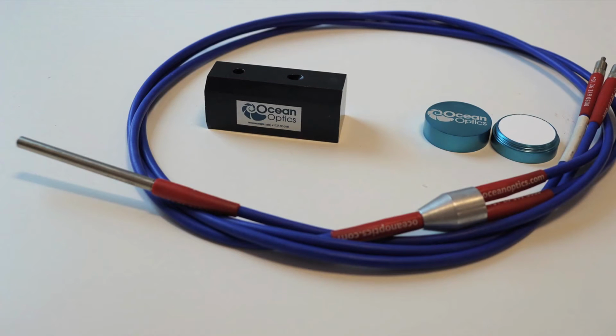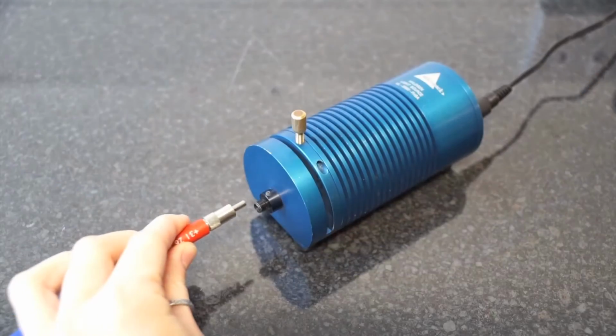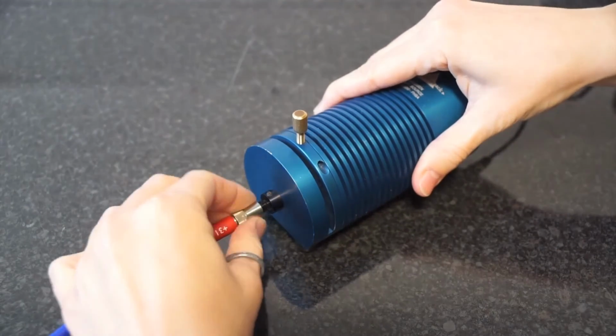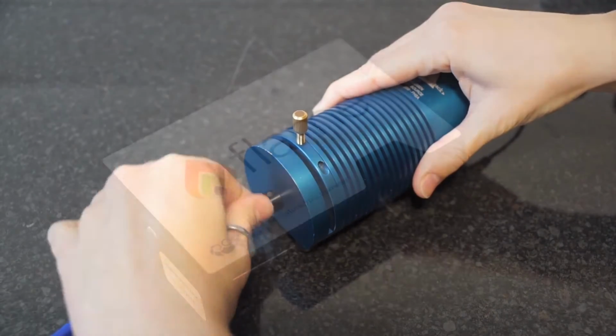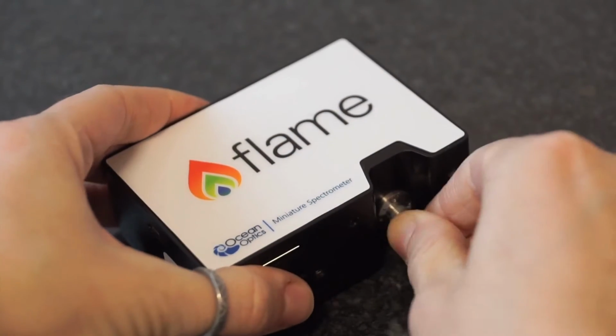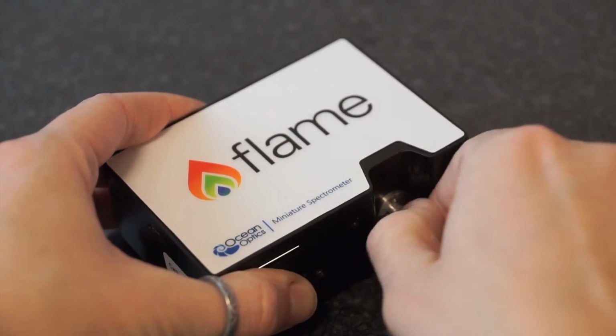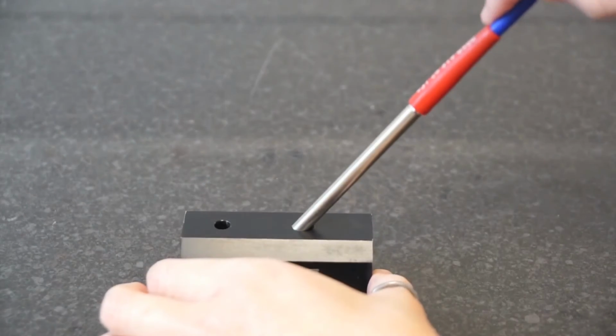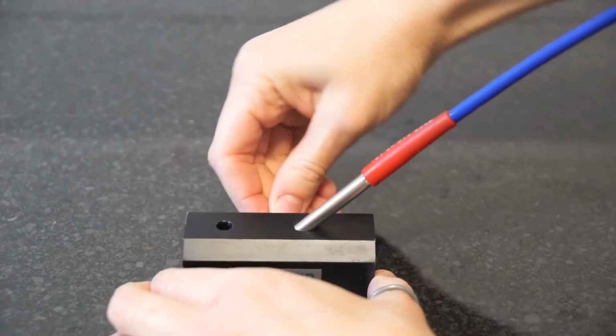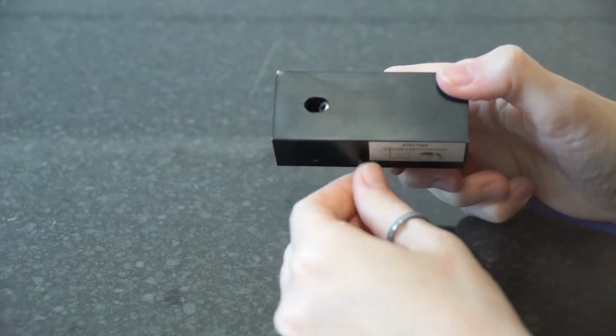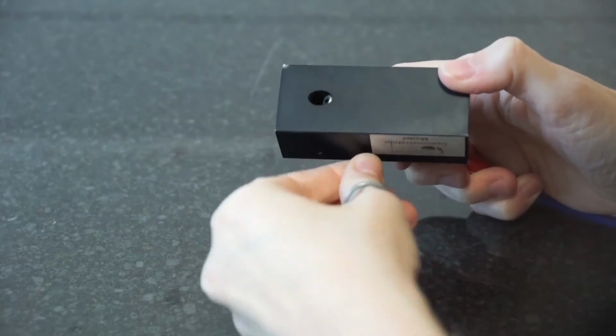To set up, start by attaching the two ends of the fibre with SMA connector to your light source and to your spectrometer. Take the end which has the circle of 6 fibres and attach it to the light source. Then attach the end with just 1 fibre to the spectrometer. Next, place the probe end into the reflection probe holder. It should be a few millimetres away from the end of the holder. The size of the measurement area will also depend on this distance.